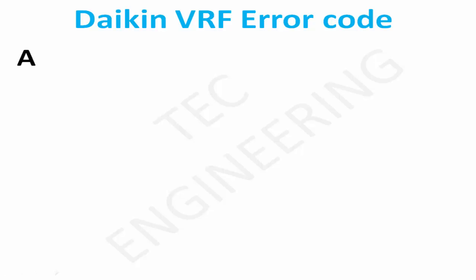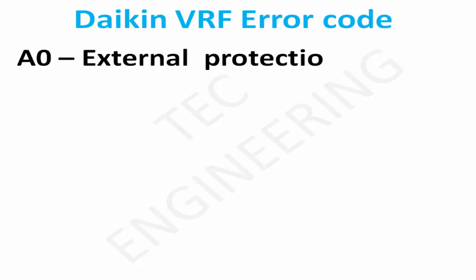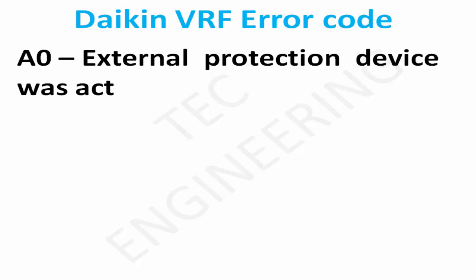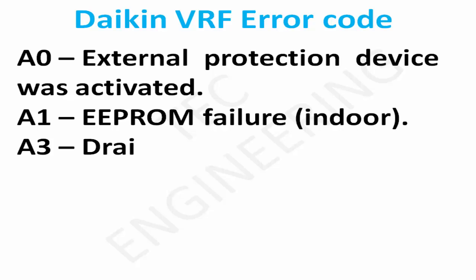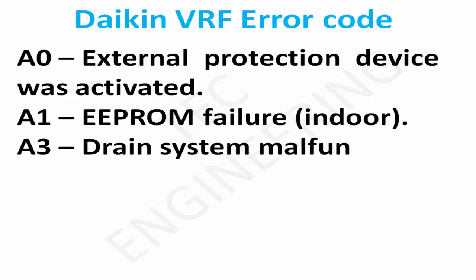A0: External protection device was activated. A1: EEPROM failure, indoor. A3: Drain system malfunction, indoor.